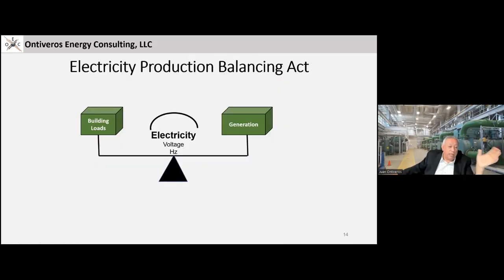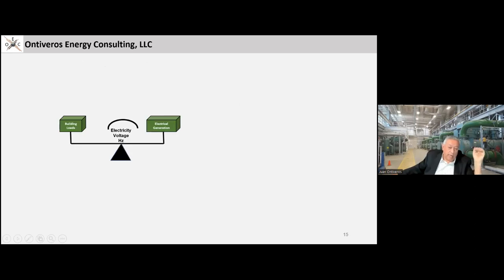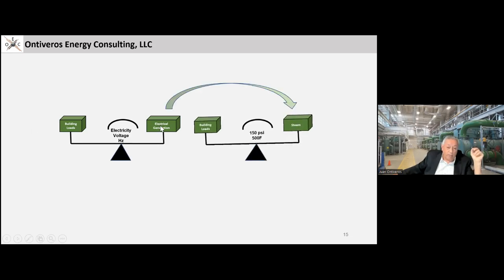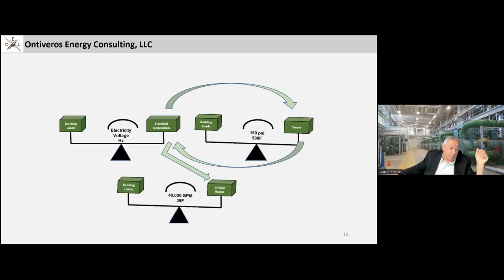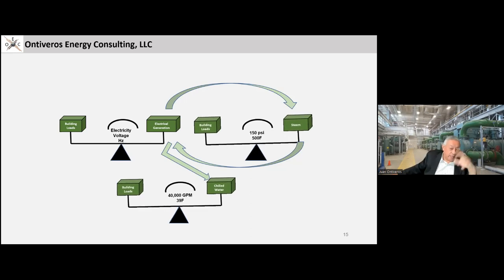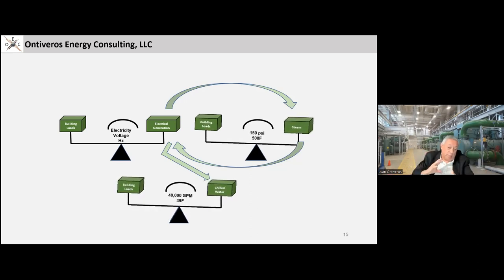So the other challenges: a typical utility is basically producing electricity and providing voltage and frequency for you to use in your facilities. They're balancing the loads against the generation. Well, if you get into systems like the microgrid that we have at UT Austin, you have the electrical generation, but the electrical generation is also making steam, which is now also serving a building load. And then that steam makes more electrical generation. So all of those are very intertwined. And then electrical generation produces chilled water. So you're balancing all three: electricity, heating, and cooling. And so it's very challenging to have all these pieces and parts working together.